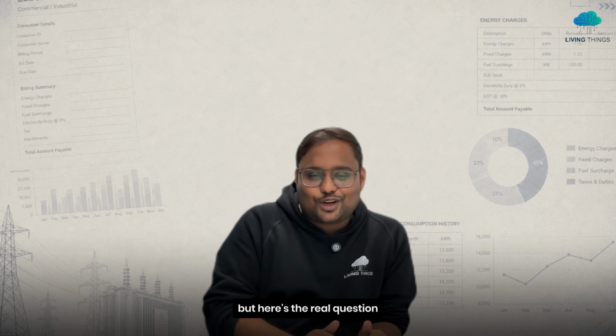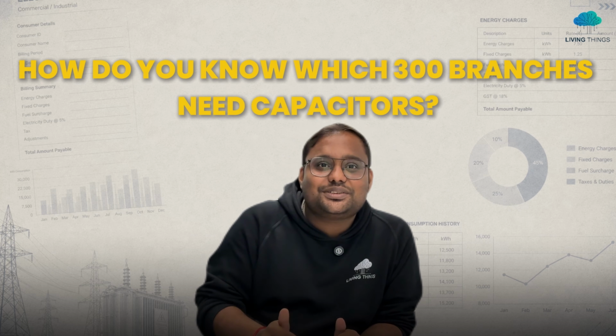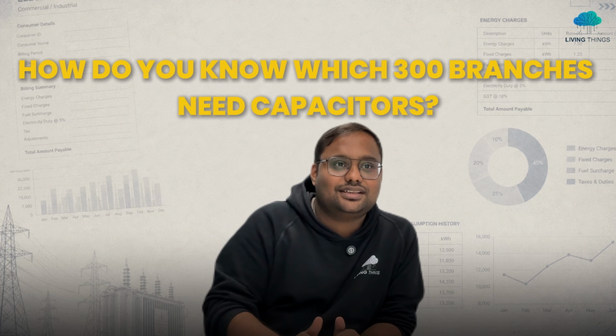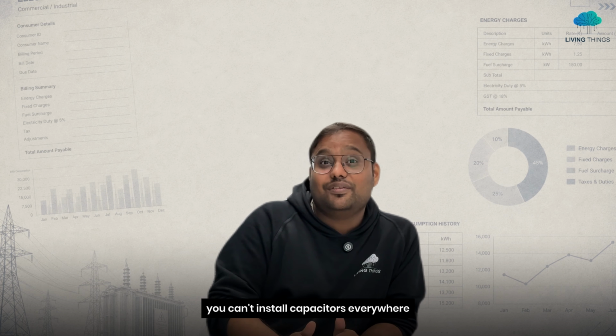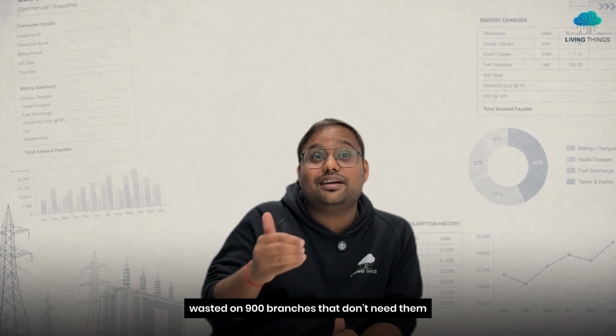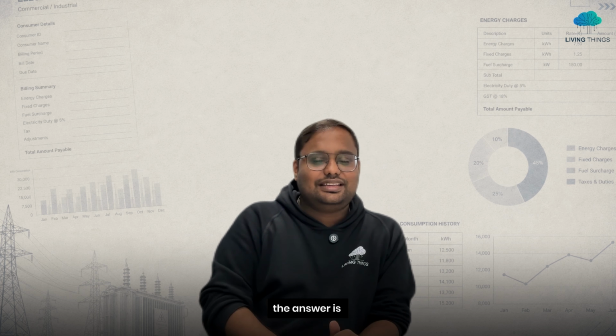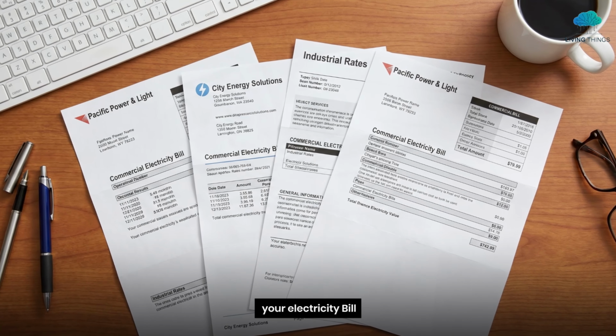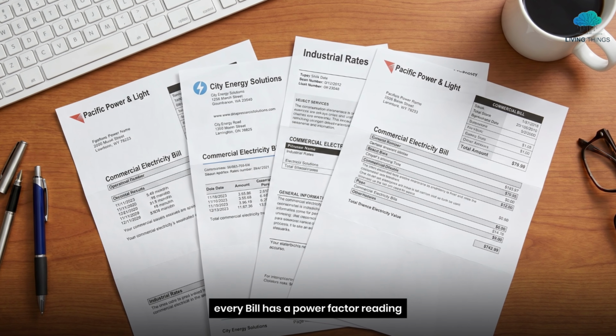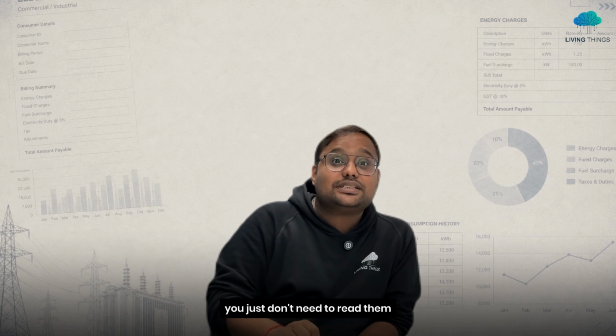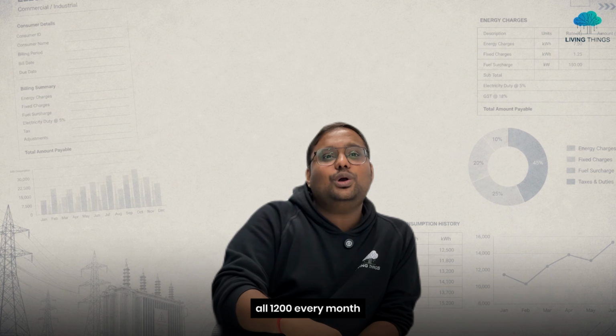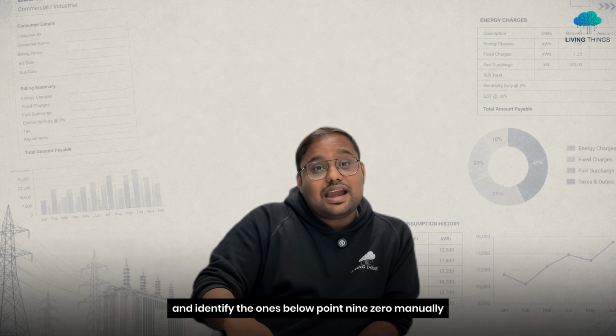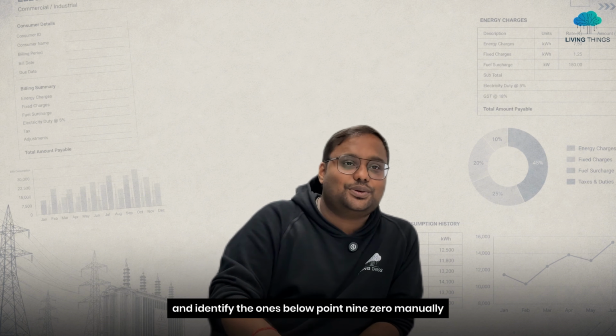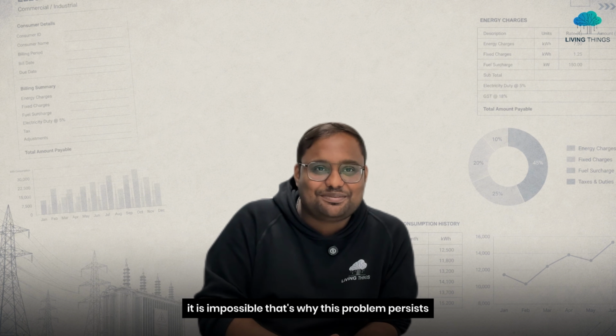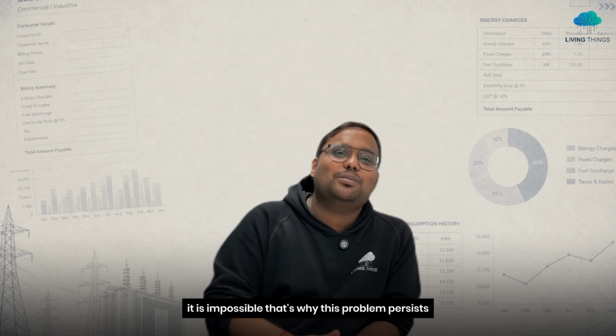But here's the real question. How do you know which 300 branches need capacitors? You have 1200 branches. You can't install capacitors everywhere. That's 4 crore wasted on 900 branches that don't need them. The answer is your electricity bill. Every bill has a power factor reading. You just need to read all 1200 every month and identify the ones below 0.90. Manually, it is impossible. That's why this problem persists.